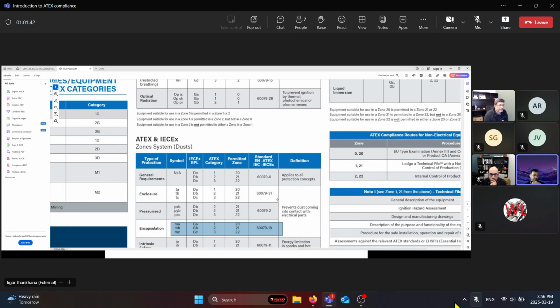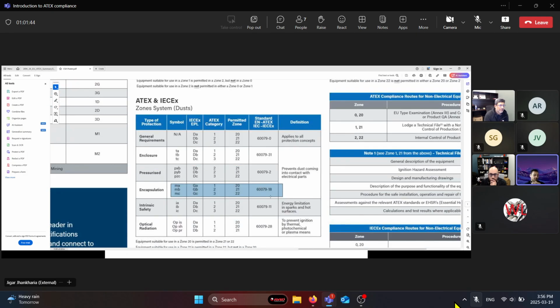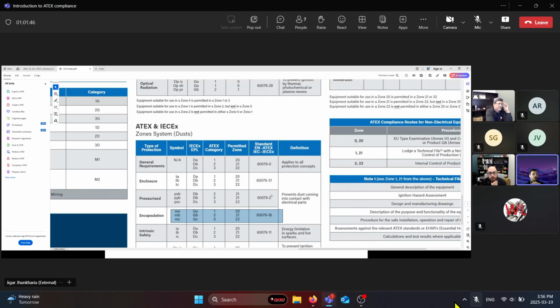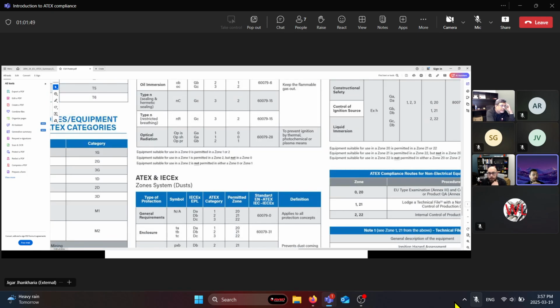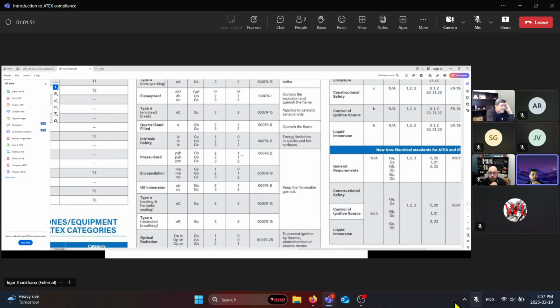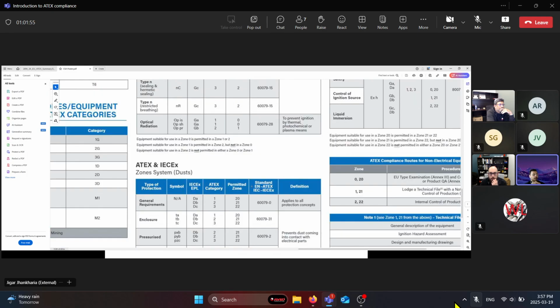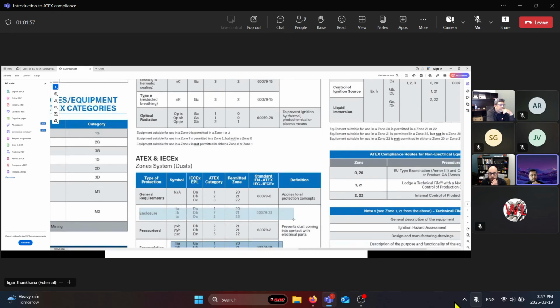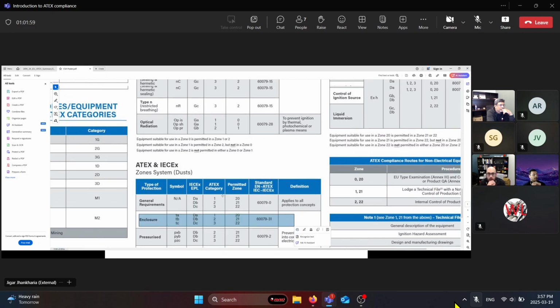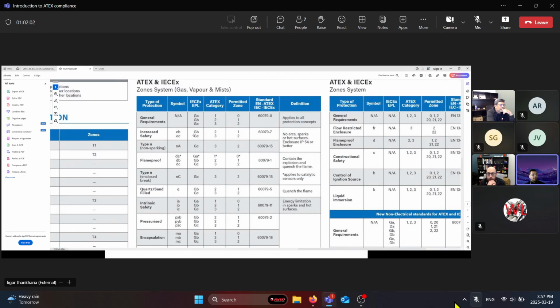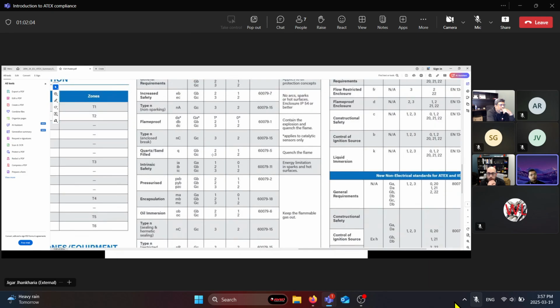So basically, like I said, encapsulation or intrinsic safety would be a better option, because then that pretty much covers your zone 1 and 2 requirements as well. Because this standard is only for enclosures for dust. There is no equivalent method of protection in the gas environment for that.